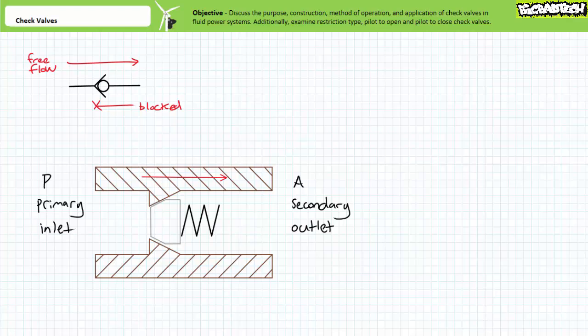Check valves often indicate the direction of free flow by scribing an arrow on the side of the valve body. The inscribed arrow is less likely to fall off than a sticker and remains readable when painted over. The schematic symbol for a check valve shows a ball on a seat because old school check valves really did use a ball rather than a poppet.